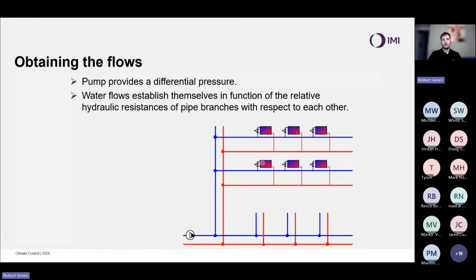I have a pump here in my plant room providing a differential pressure. It is providing a difference in static pressure between the inlet and outlet of the pump. What then happens is my water flows in my systems are going to establish themselves in function of the relative resistance of the branches in respect to each other.